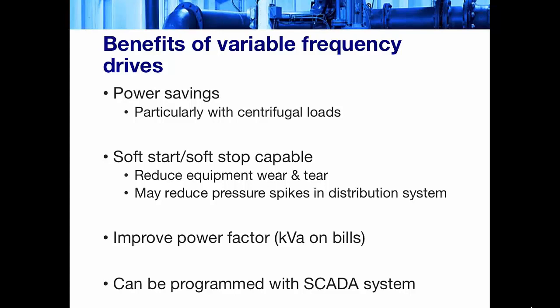So basically, you slowly turn on your equipment and you eliminate the sudden input of power that across the line voltage does. So this reduces equipment wear and tear, so your pumps will last a little bit longer. And you can also reduce pressure spikes within your distribution system. There are some case studies of distribution systems that go from something like 20 main breaks a year, they install VFDs and they're down to 1 without any other changes.